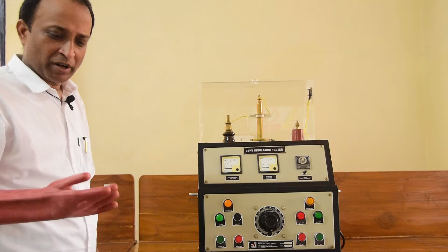So for testing the paper, a pair of electrodes which consist of this particular central assembly. Here in this assembly we have got two terminals. So I'll just show you. Whenever we are working with the high voltage terminals, it is a good practice to have safety gloves in our hands, because there may be static charges left out, although this unit is unenergized. But still, while working on this, it is a good practice that we use the rubber gloves. These are rated for 11 kV. Okay, so please observe that this is a top electrode.